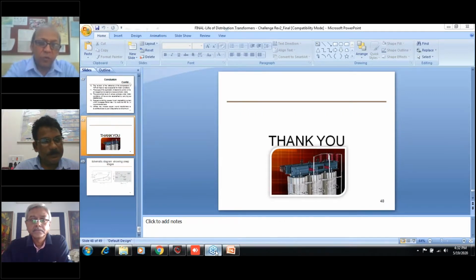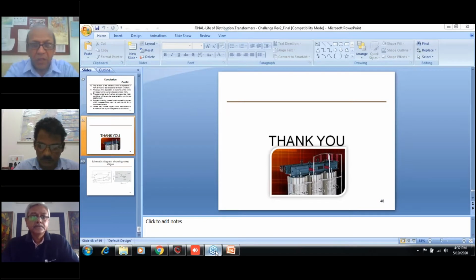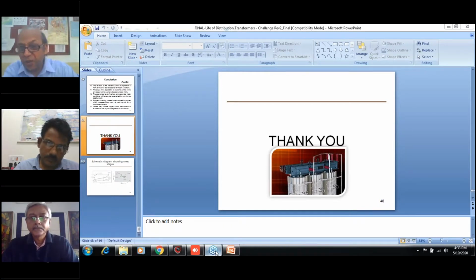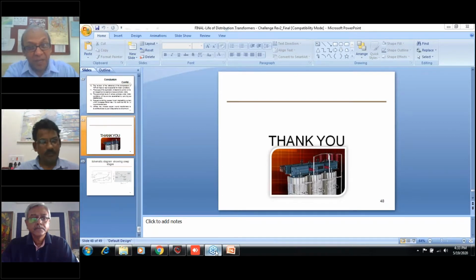Again, if you see, there are wind energy transformers where the metal parts of the bushing were failing. Why were they failing? There are vibrations because of the presence of harmonics. It is not only the loss that we directly see; higher loss is due to harmonics. That part we see, but we don't consider that there is also mechanical vibration from the same harmonics in the metal parts of the transformer or other devices. They are eroding, and this needs to be studied.